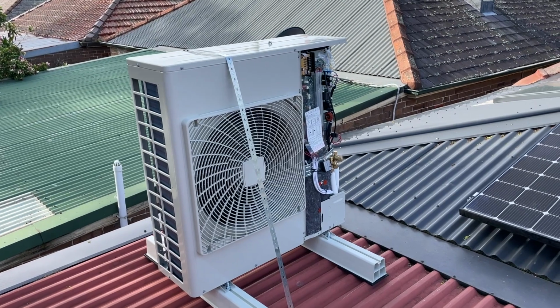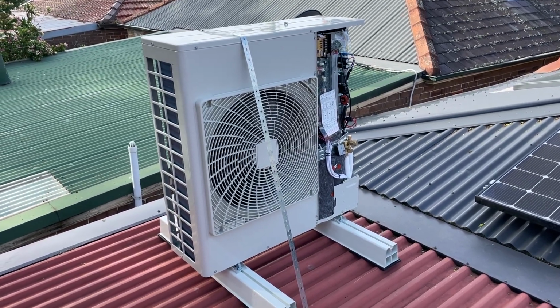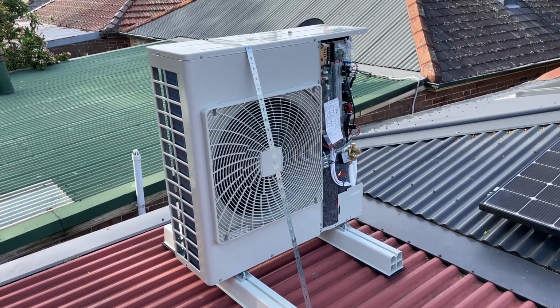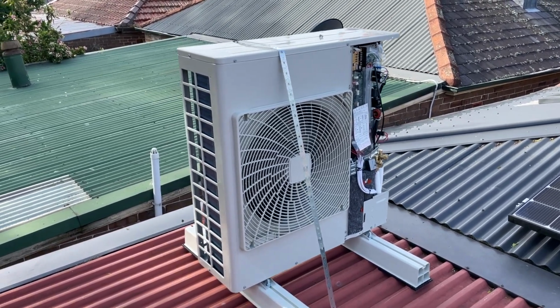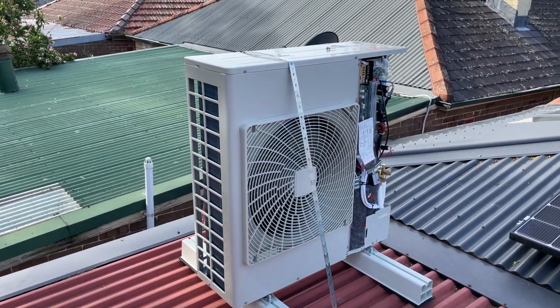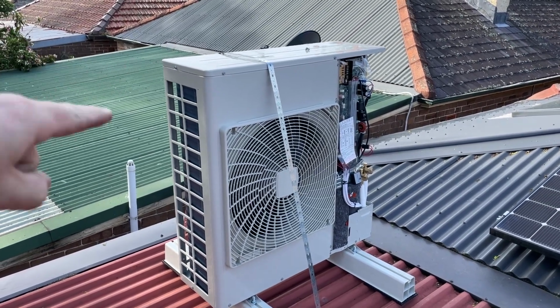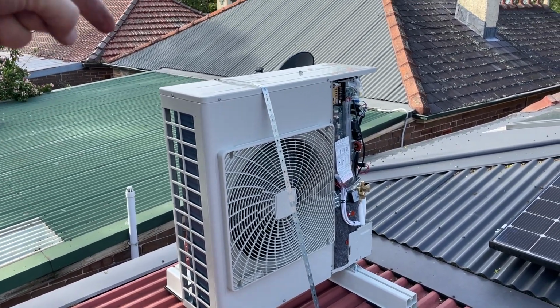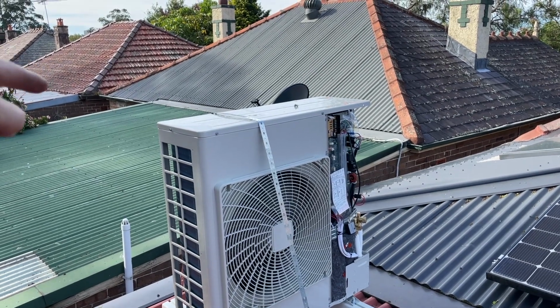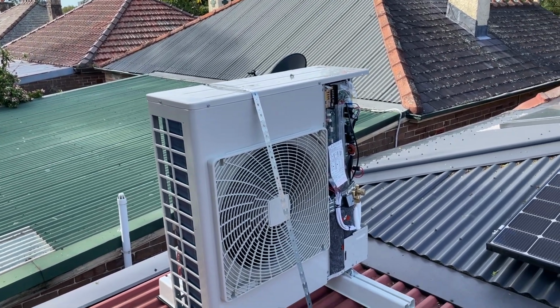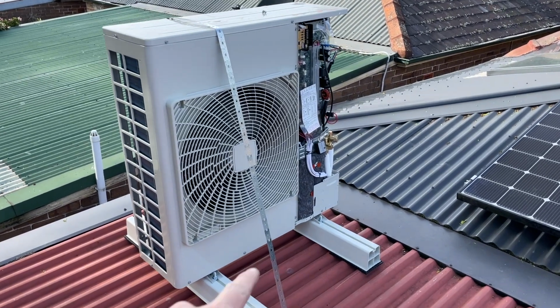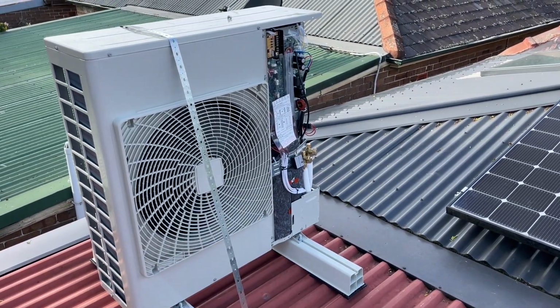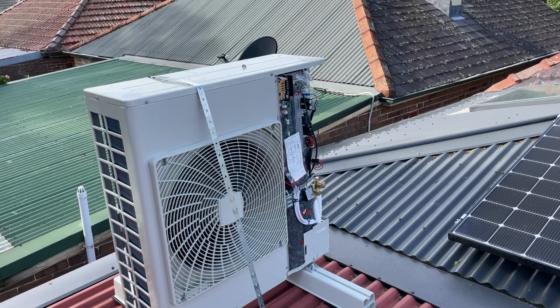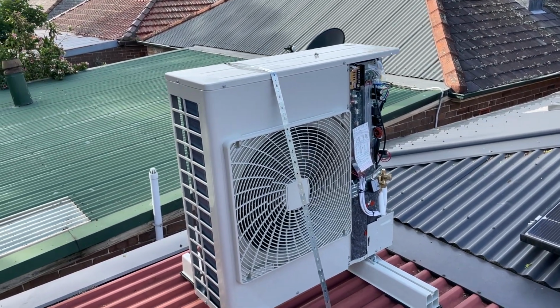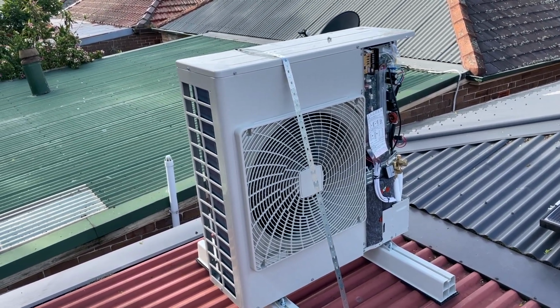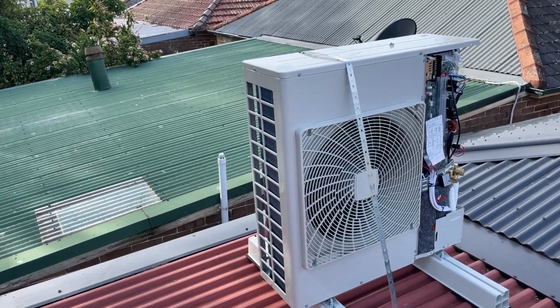So basically, if you're going to get this tool and start using it, it's a little bit confusing if you don't know where the sensors are located and what they're called. For example, this unit's got 3 sensors: it gets an outdoor air temperature from one of the sensors on the back of the unit, and then inside it's got a sensor on the other side of that liquid 4-way valve, and it's also got a temperature sensor on the pipe that comes off the outdoor coil.